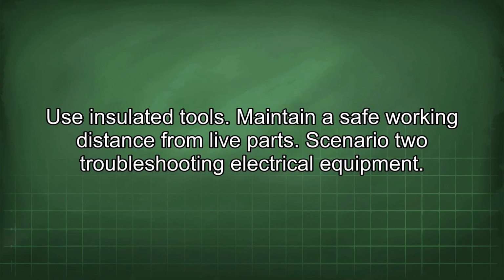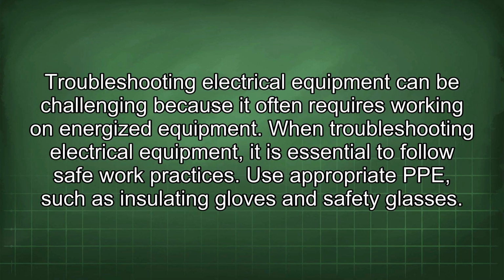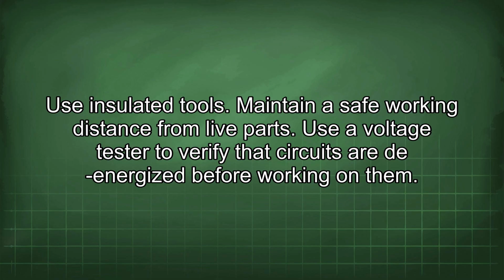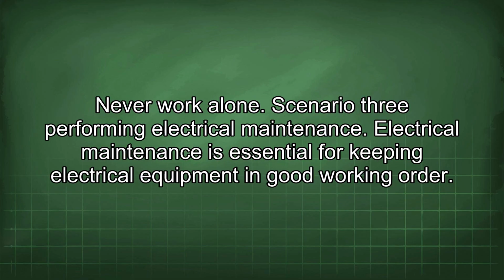Scenario 2. Troubleshooting electrical equipment. Troubleshooting electrical equipment can be challenging because it often requires working on energized equipment. When troubleshooting electrical equipment, it is essential to follow safe work practices. Use appropriate PPE such as insulating gloves and safety glasses. Use insulated tools. Maintain a safe working distance from live parts. Use a voltage tester to verify that circuits are de-energized before working on them. Never work alone.